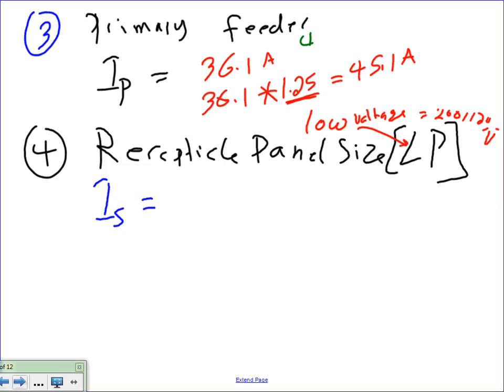Then you take the 45.1 amps, take it to Table 310.15(B)(16), under the 75-degree column. You always go to 75, Chris. That's your default because we're three-phase. Equipment that is three-phase is almost always rated for 75 degrees. No question asked. We're three-phase here. So you go to 75.